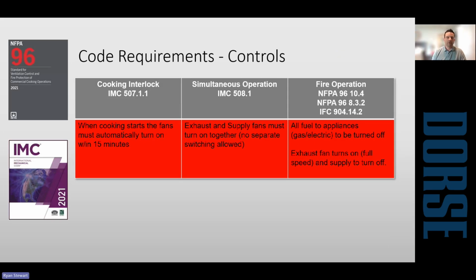So codes related to controls, they require an interlock, and they want it to be automatic. They give you basically 15 minutes from the time that an appliance turns on and produces heat to activate the fans. And they want the exhaust and supply fan to turn on together, so no separate switching is allowed. And then in a fire condition, they want to see that the gas and electrical turn off and the exhaust fan runs to full speed and the makeup air shuts down.